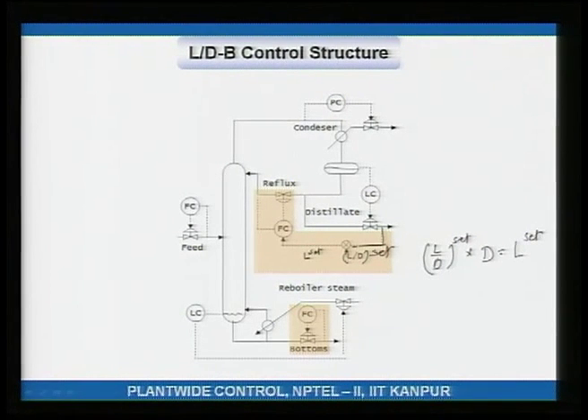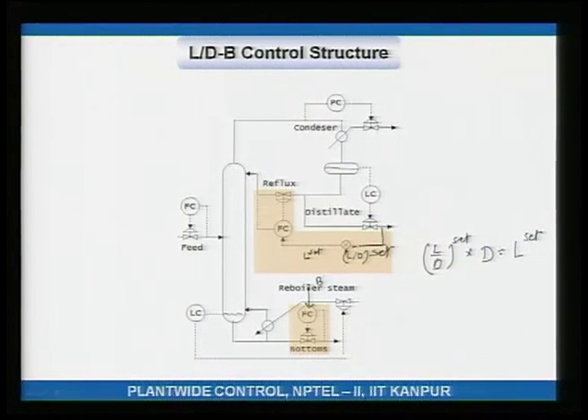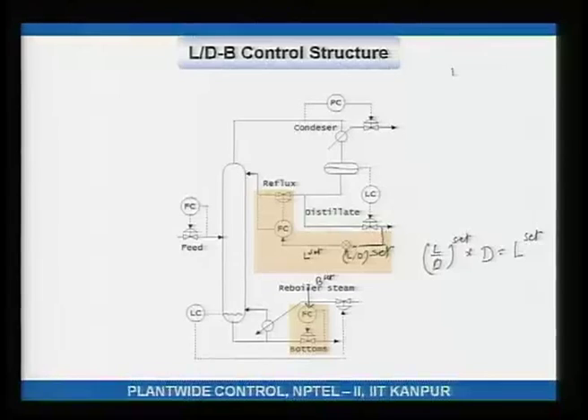At the bottom, if the bottom level is controlled using reboiler duty, the operator sets the bottoms B set point and the L/D set point to get the desired separation — hence this is called the L/D, B structure.